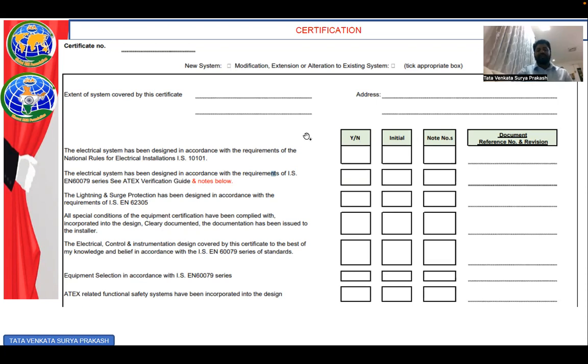That is a very critical part. On the project side, we do SIL studies. The SIL studies follow two stages: one is the assessment stage, then the determination stage. Verification is done by the approved agency through the approved certification body. So each equipment will be SIL rated and certified, meaning that particular equipment is certified for its functional safety requirement rating.